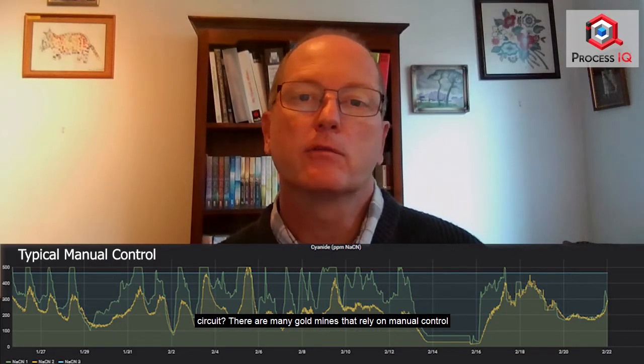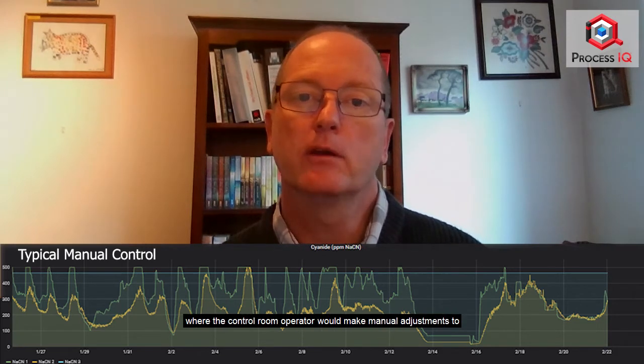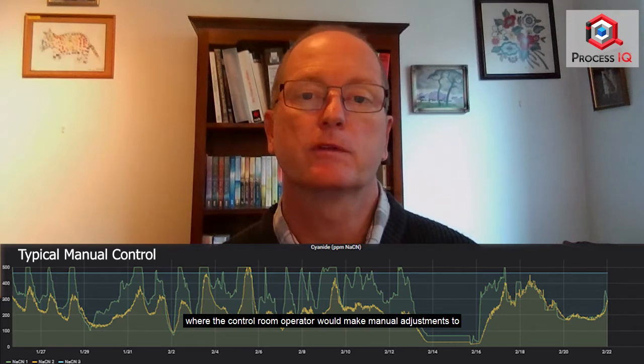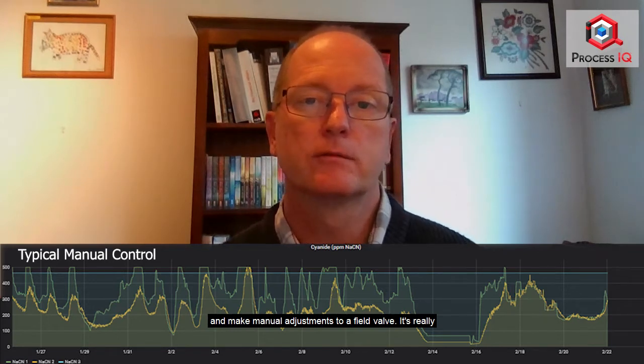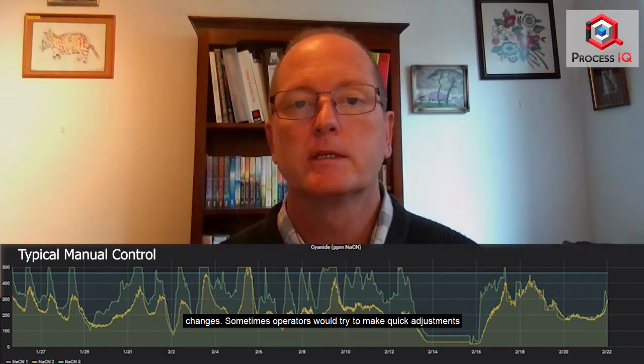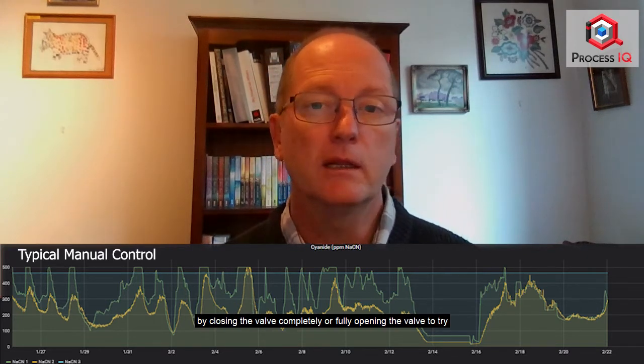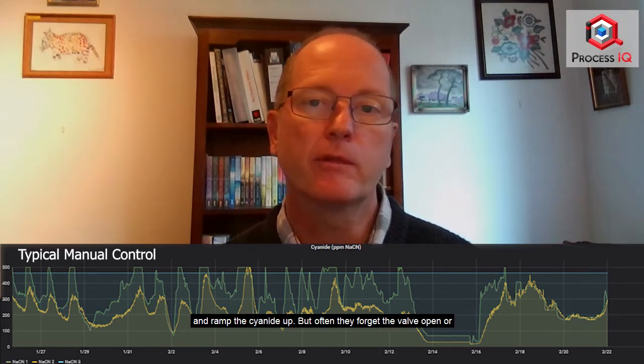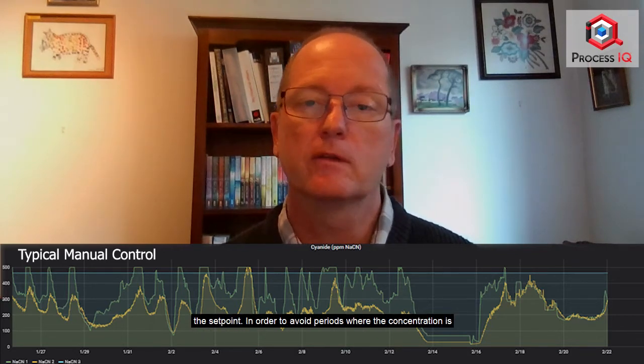So how do gold mines typically control cyanide in their leach circuit? There are many gold mines that rely on manual control where the control room operator would make manual adjustments to a control valve, or they would send an operator into the field to make manual adjustments to a field valve. It's really difficult to keep the concentration at set point because of the long residence times in the leach tanks. You can take sometimes hours before you see the full extent of your changes. Sometimes operators would try to make quick adjustments by closing the valve completely or fully opening the valve to try and ramp the cyanide up, but often they forget the valve is opened or closed and they are overshooting or undershooting the set point.